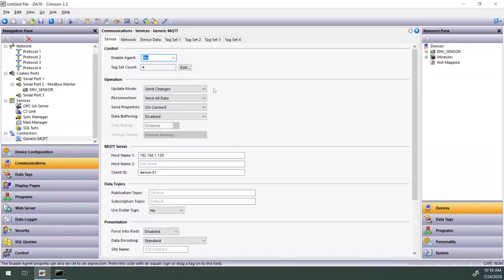Now, a couple things here. There are several settings here we could talk about, but I want to focus on the main, the greatest hits of MQTT, if you will. Number 1 is the update mode, send changes. This is where you will get some of your biggest benefits from MQTT, just by nature of saving bandwidth. If you think about something like Modbus, it's a poll and response protocol, meaning it's constantly polling, and there's constantly responses if things are working correctly. Even if you have, say, a tank level sitting at 10 feet for 2 days, that whole 2 days it's constantly polling and responding with that current level.